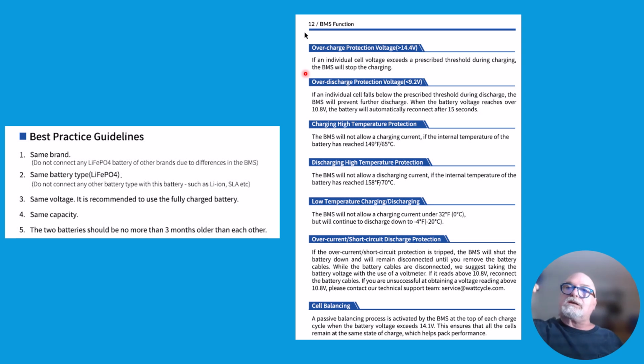It happens at a very low current, and you're still attached to the loads. So if you have any loads, you're not going to get a spike, because that spike is going to feed the loads. So charge current is turned off. The worst thing you're going to see is maybe a high voltage alarm if you're charging from an old school or quality inverter charger, which is low frequency, because it uses a big toroidal transformer in there. You might see a brief voltage spike, which could set off an alarm. There's nothing to worry about. It's a very brief spike when the charging shuts off, if you have no loads and the charger can't dissipate that into the loads. If you're just charging the battery, you may set off a high voltage alarm. That's all.